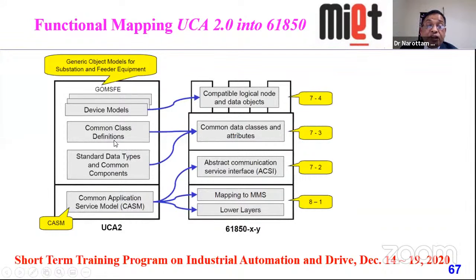Then common class definition also comes with UCA2, and common data class and attributes at level 7 — we'll come to the levels soon — and standard data types and common components at level 7. Then common application and service model links with IEC standards level 7 and level 8. Level 7 is abstract communication service interface, ACSI, mapping to MMS and lower layers. So this is the link between UCA 2 and IEC 61850.